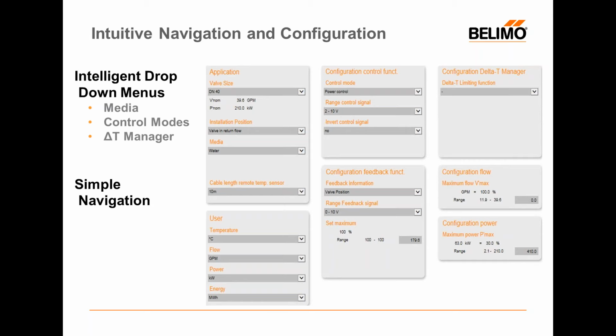And if we look at these blocks from top left down to the bottom right, you can see the first one, application, is pretty basic stuff. The valve size itself, installation position, whether it be in the return or supply line of the air handler. That is important so we calculate our BTUs correctly and we know that we're in a cooling mode for a chilled water application.